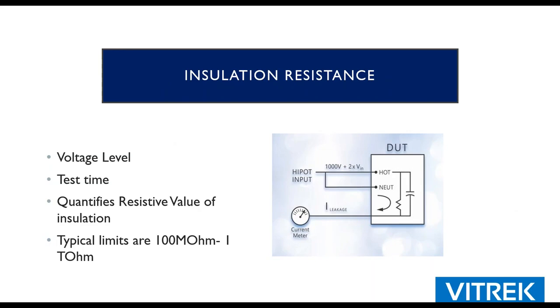So the other common test is insulation resistance, DCIR. Some people might call it a Megger test, because the Megger company kind of made that test famous. It's almost always a DC test, although it doesn't have to be. The voltage levels for insulation resistance are typically going to be lower than that of a Hipot test. In a Hipot test, your goal is to stress the insulation, possibly to the point of failure. And in an insulation resistance test, the objective is to quantify the value of the insulation.